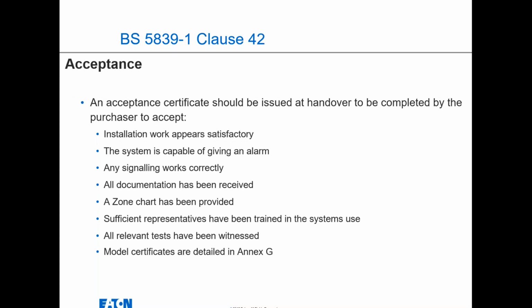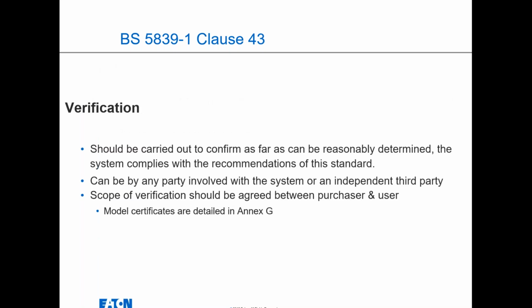Again, they talk about an acceptance certificate. I don't think I've ever seen one, but the client should sign off and say he's accepted the fire alarm system. That generally is never done, but it's part of the documentation. I don't think it would be a problem if it wasn't done. In terms of importance, the key factor is the design, install, and commissioning certification. And we touched on the verification certificate earlier. That needs to be something that you can use for any changes further down the line after the install.